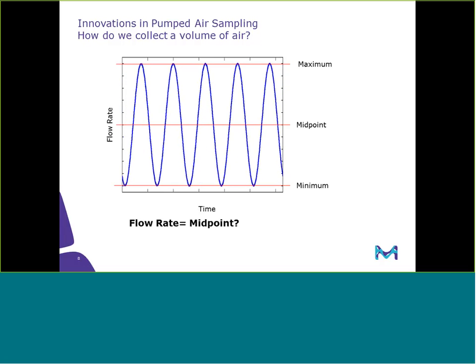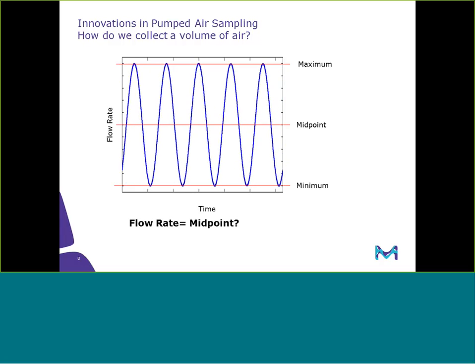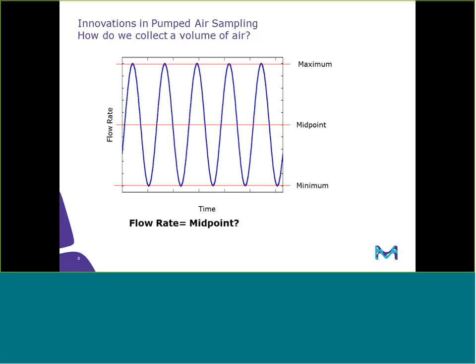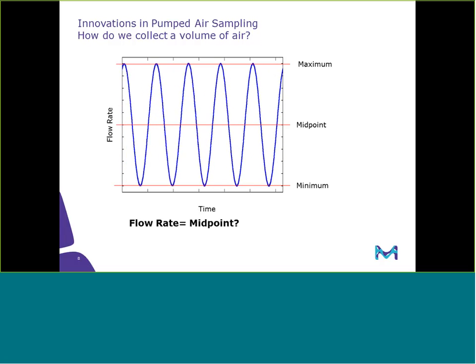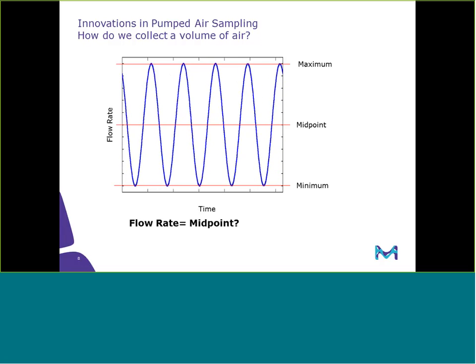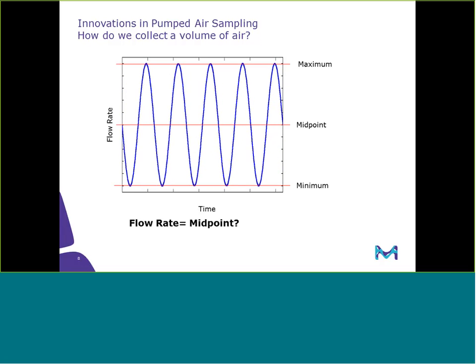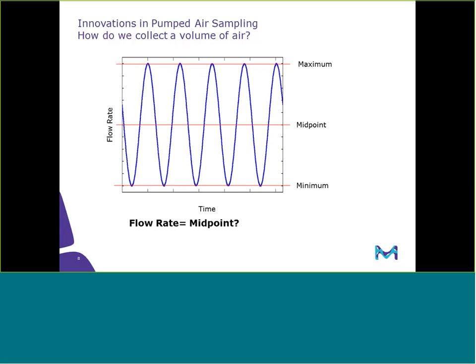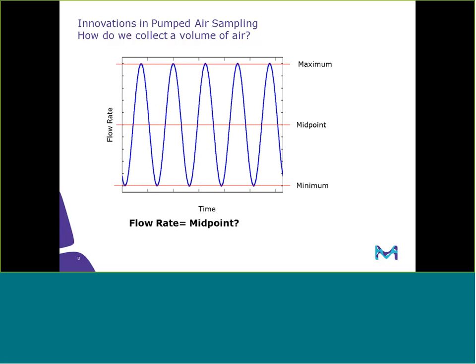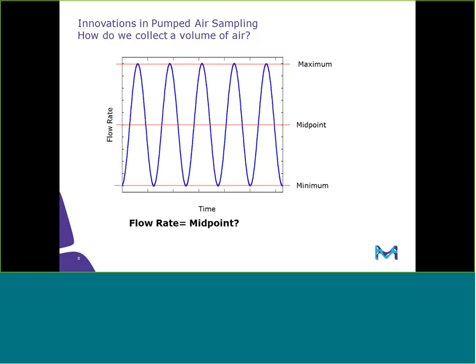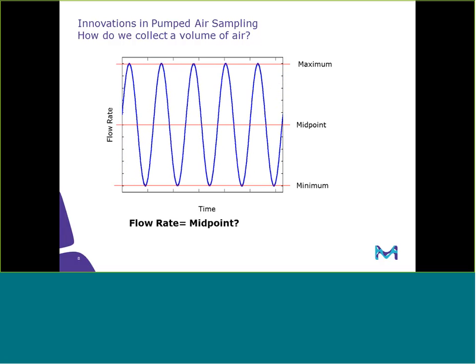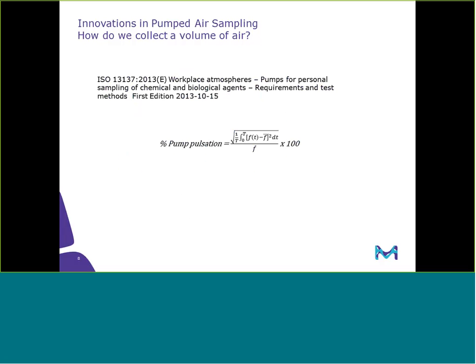Nevertheless, if the flow rate of the air sampling pump is not accurately controlled, if there are large pulsation waves, or if the pulsation waveform is non-ideal, the collected volume of air could be highly inaccurate, which could give an under or overestimation of the final concentration value of your air sample.